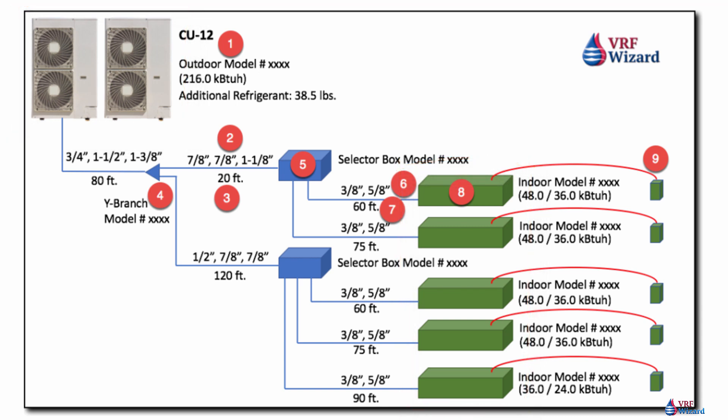On most of the software, you'll have to choose the indoor unit and the software program will pick the appropriate outdoor units, or give you options to pick from various outdoor units. The piping diagram will also show pipe sizes and lengths used in the calculations. You will be asked to enter the lengths of the piping, and the software will automatically indicate whether the design has exceeded the allowable lengths as dictated by the VRF manufacturer.